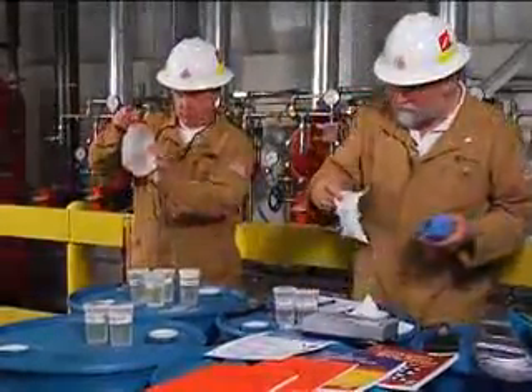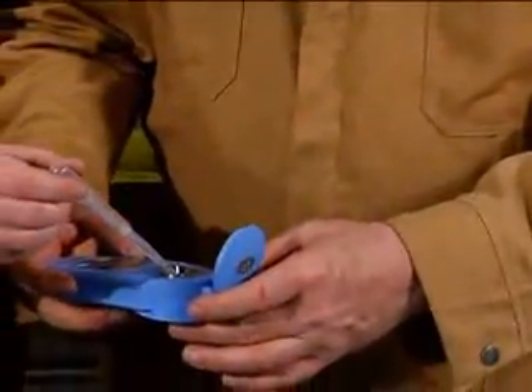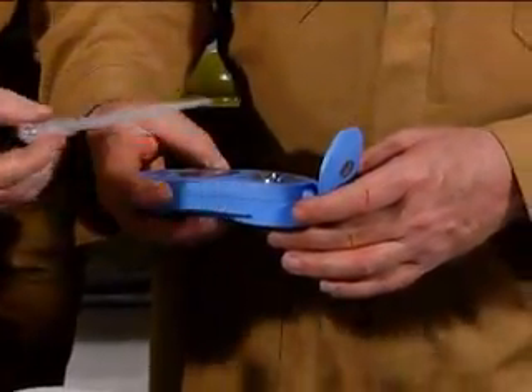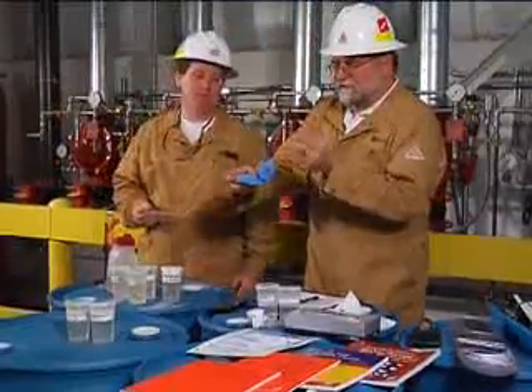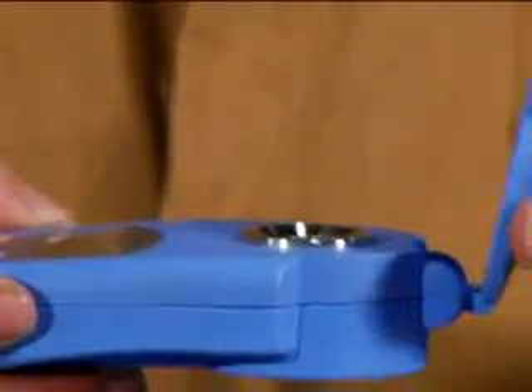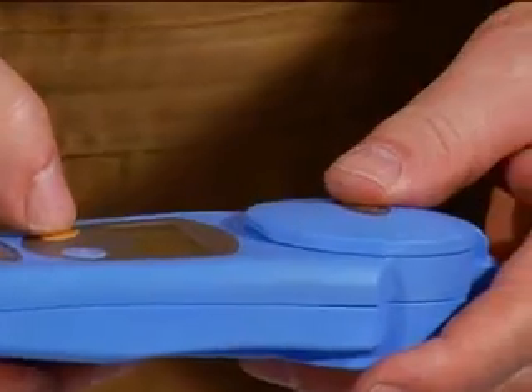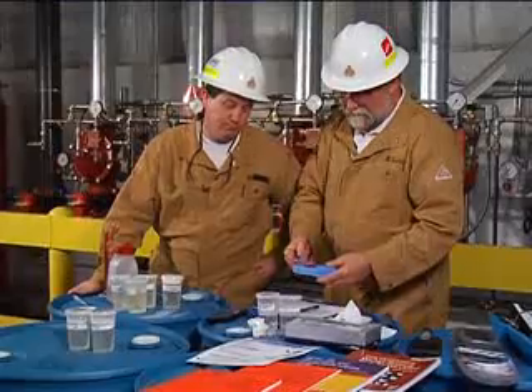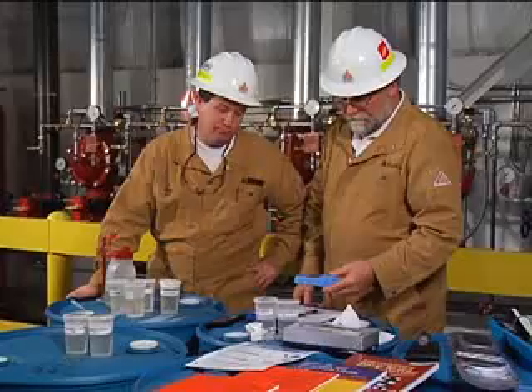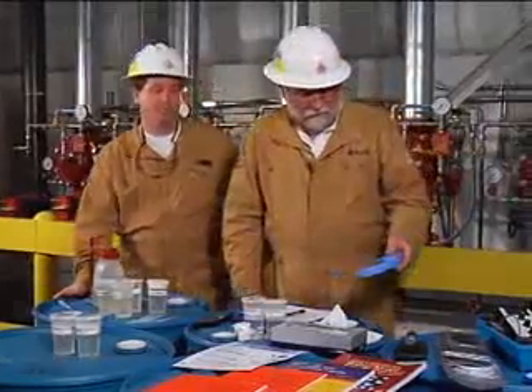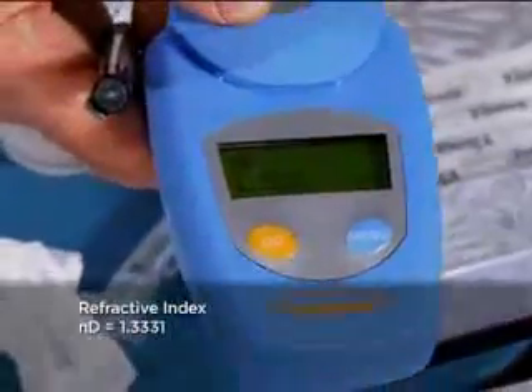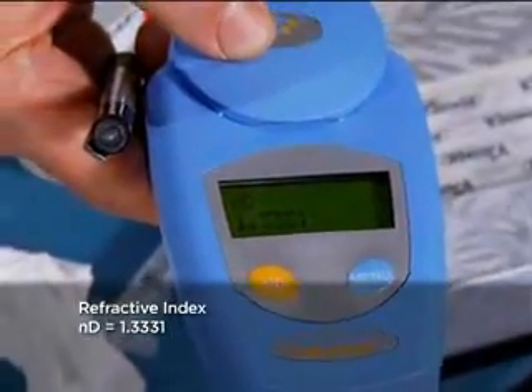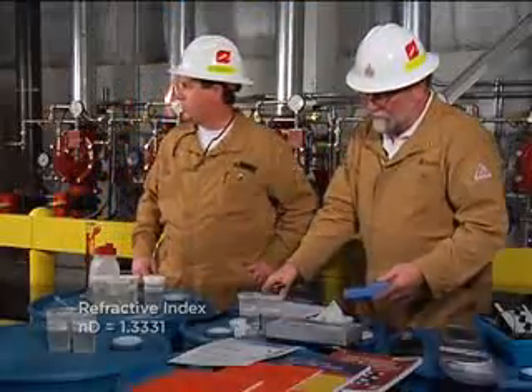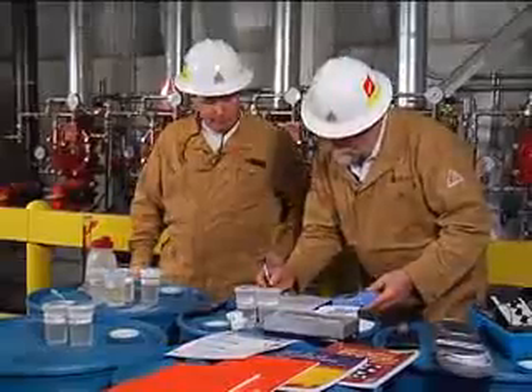First thing we're going to do is test water. We fill this conical shaped sample container about halfway up, close the lens, and hit a button that says go. The refractometer gives us a reading of the water being 1.3331. I record that information on the form that I'm using.